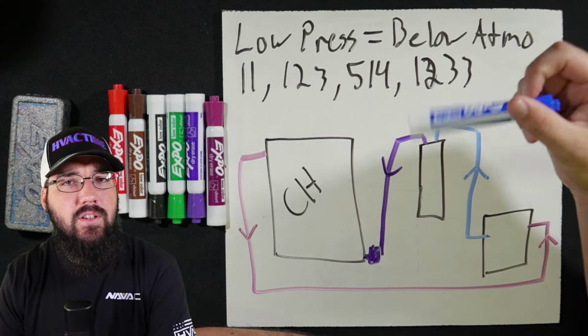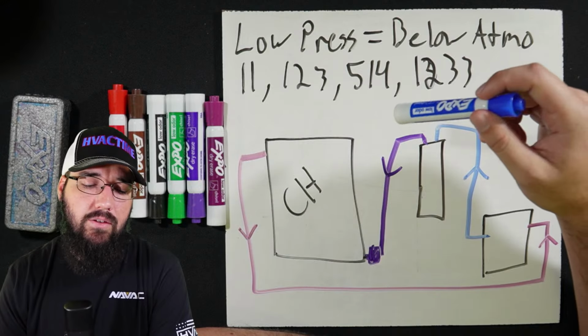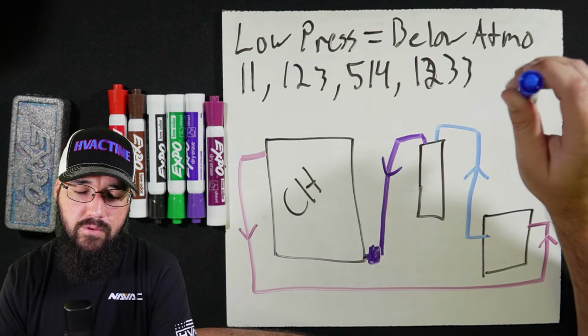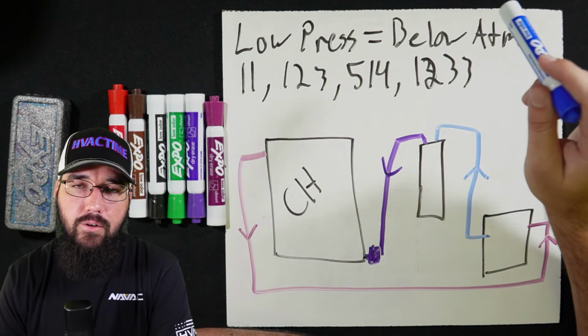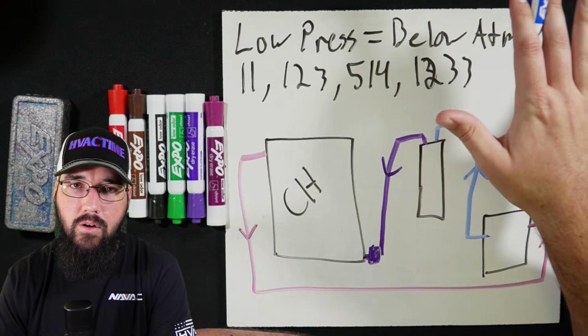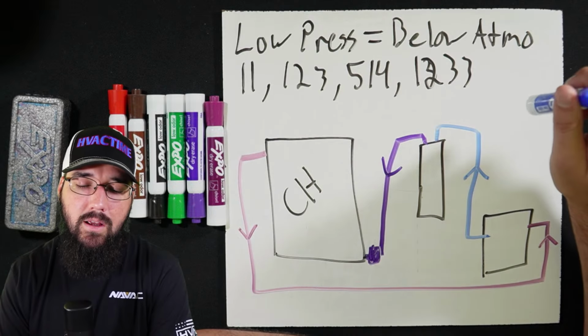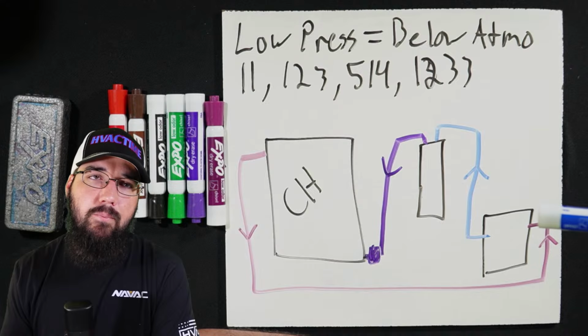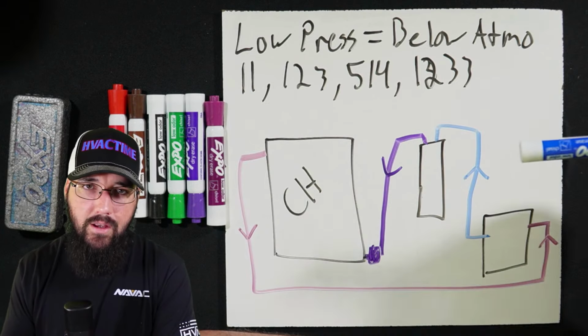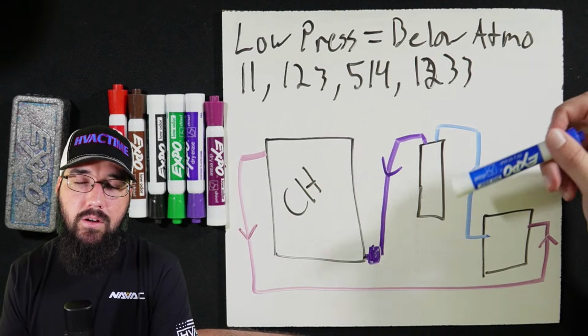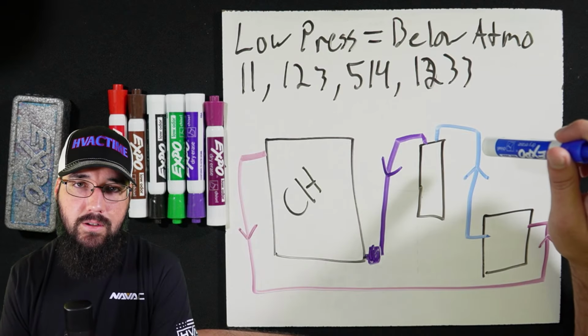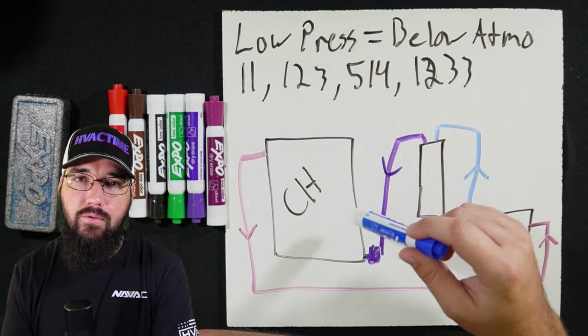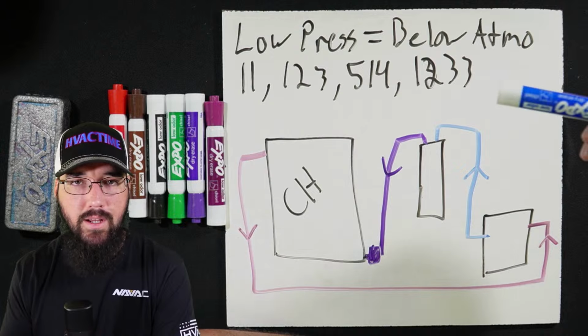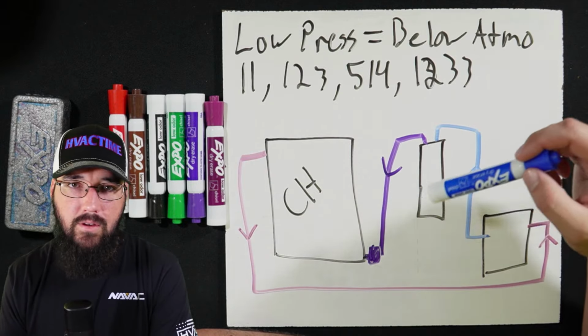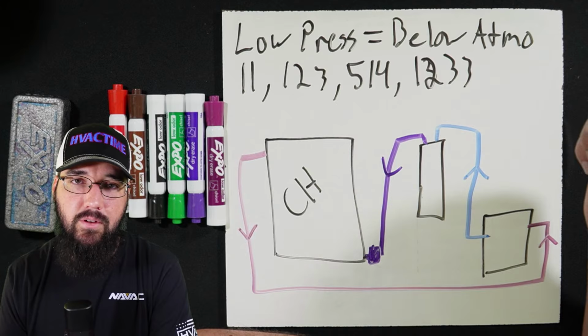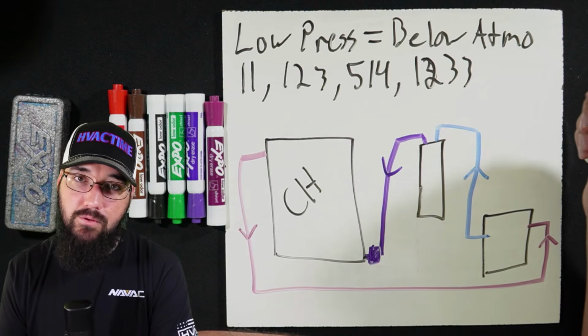So pre-charging doesn't negate needing to flow water. I still push that you don't want to flow water during your pressure test. You don't want to flow water during repairs. You don't want to flow water during evacuation. Have that water isolated and not moving. But when you get to the point of needing to charge, and this is true for recovery, then you turn the pumps on or open the isolation valve, get water moving through the machine. Protect your tubes. Pre-charging with vapor only helps protect the tubes further. It's crazy how expensive it is to try to fix and clean up a flooded machine. Let's just not do that, okay?